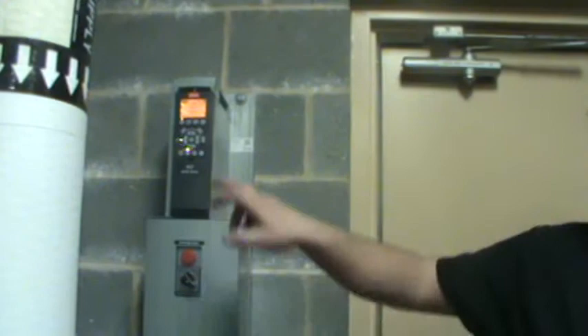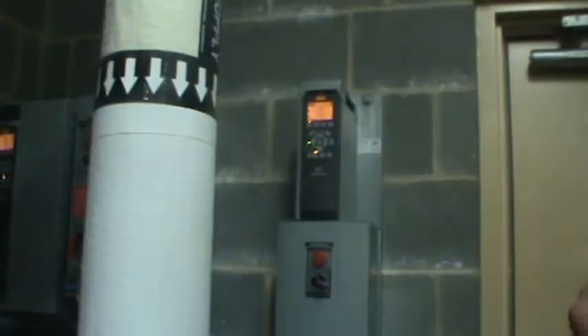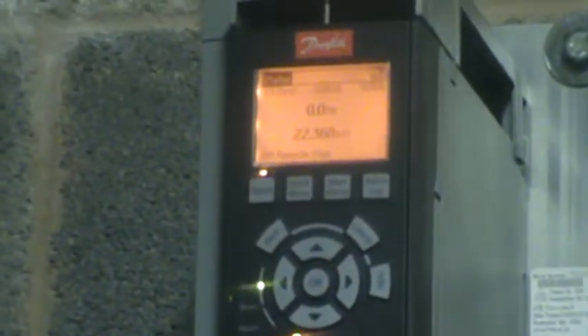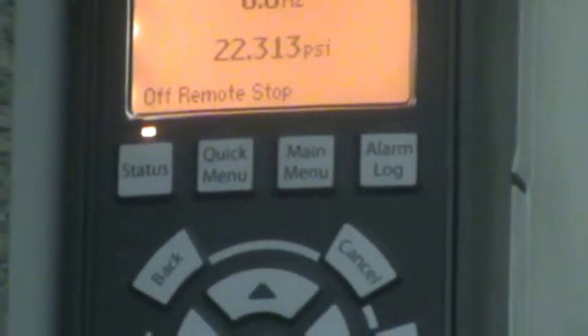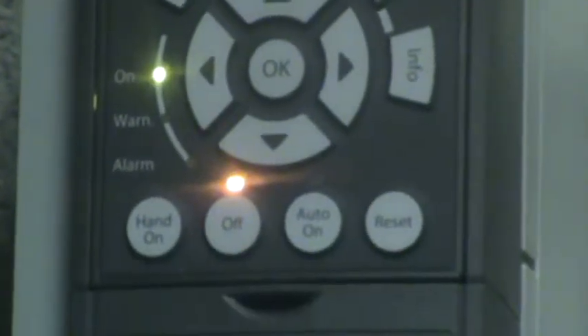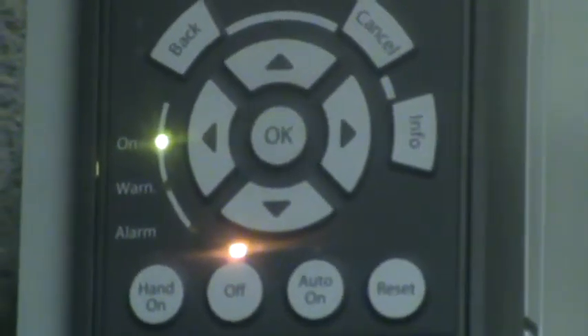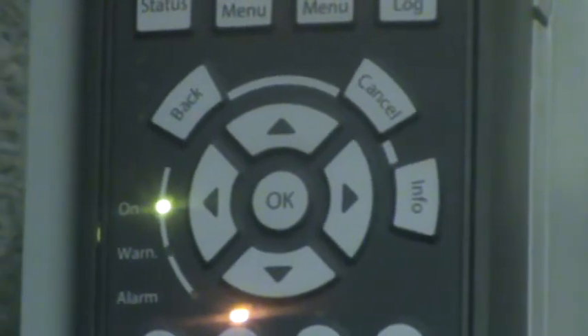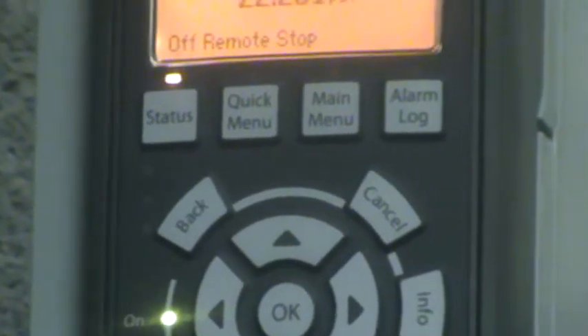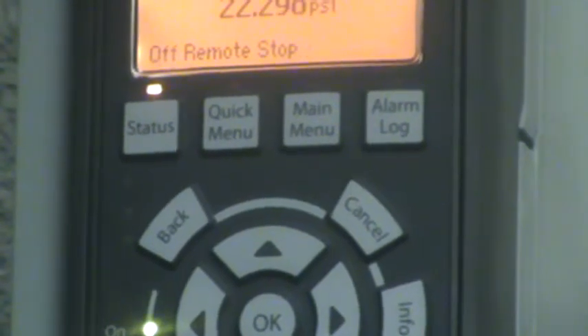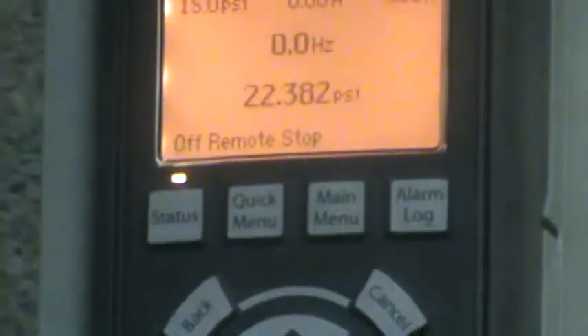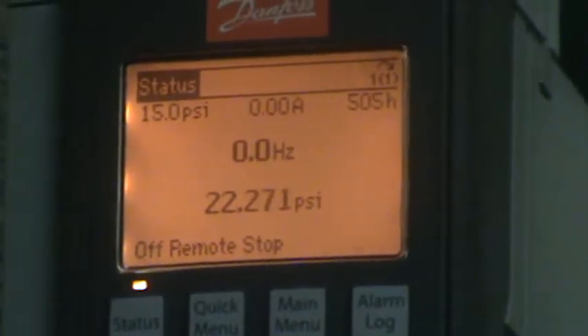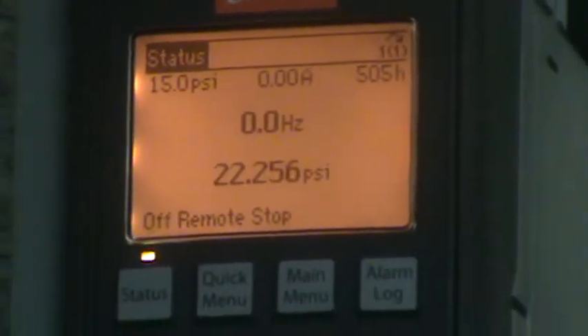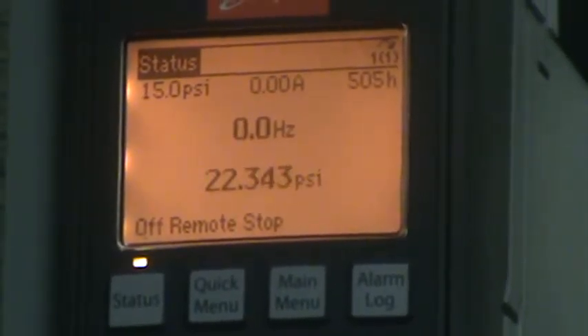If you see the phase loss thing, hit the info button here, and it'll give you a little section you can actually scroll down and read, and they'll tell you where to start looking for issues. They use European standards for their phasing out to the motor, so they'll say U, V or W, and 1, 2, 3 for the inside. So if it tells you W phase is lost, you lost L3. You pull the cover up here, look at 3, trace it over here, and then you just go into basic electrical testing, troubleshooting, find out what happened, where'd your power go? Did your contactor burn out, did the wire break, did your motor take a crap? That just comes down to electrical work there.